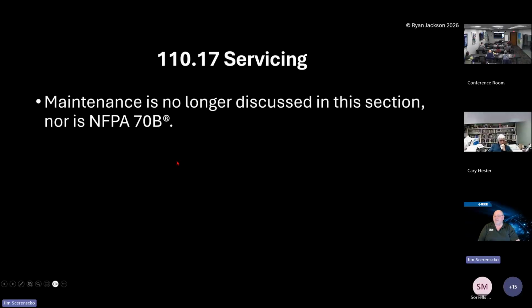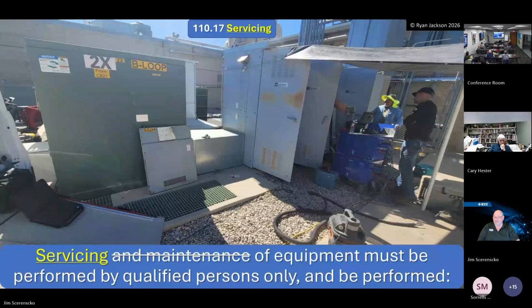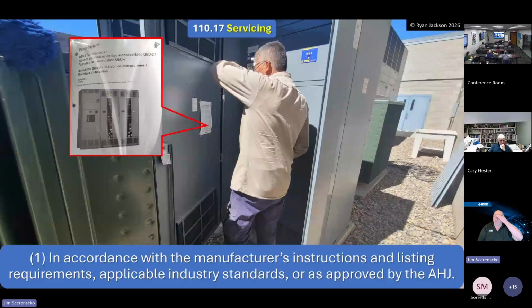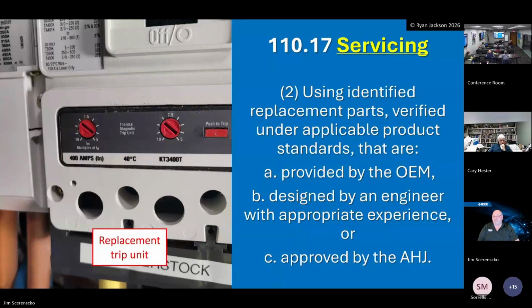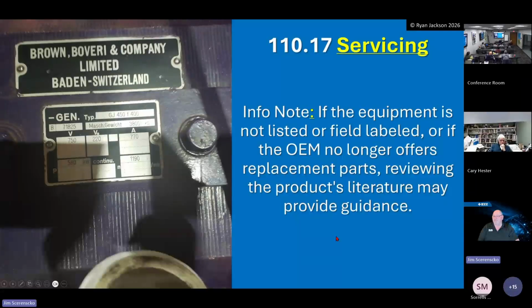110.17 for servicing: maintenance is no longer discussed in this section, nor is NFPA 70B. So servicing, not maintenance. Maintenance falls under 70B, not under the NEC. Servicing of equipment must be performed by qualified persons only and be performed in accordance with the manufacturer's instructions and listings. So if you're going to do something to the equipment, you need to provide to us what is required by the manufacturer to bring it back to its original listing. Servicing also covers a replacement trip unit provided by the original equipment manufacturer and approved by the AHJ. All this stuff falls under servicing.